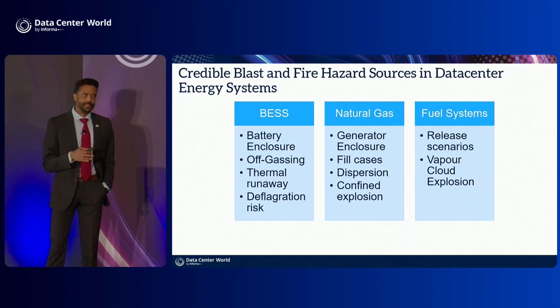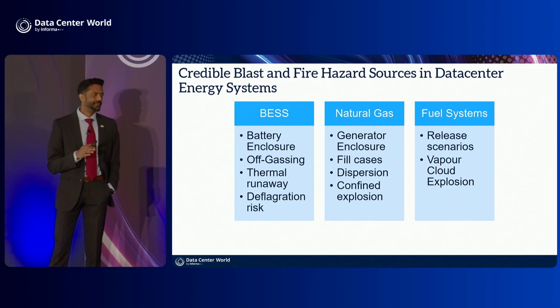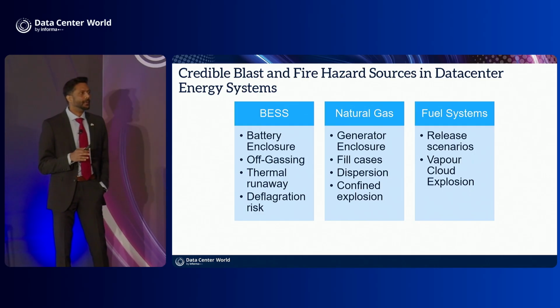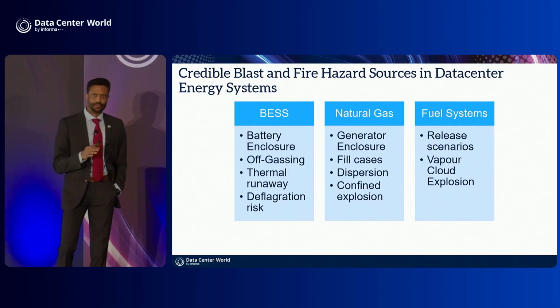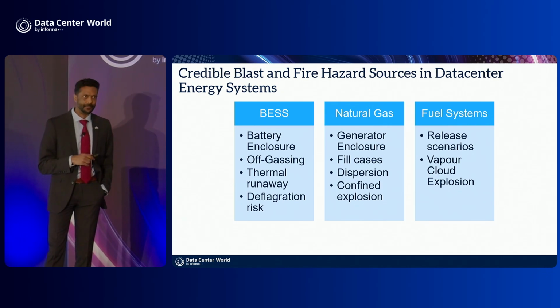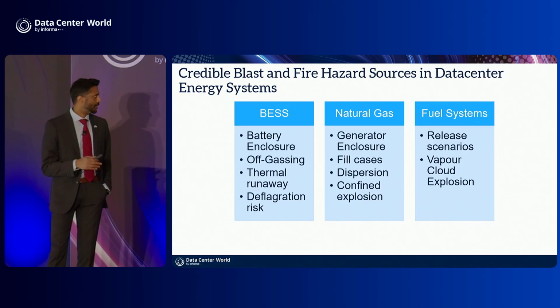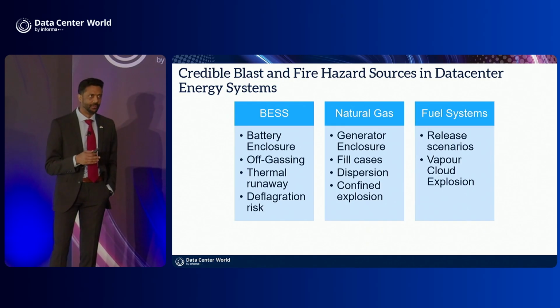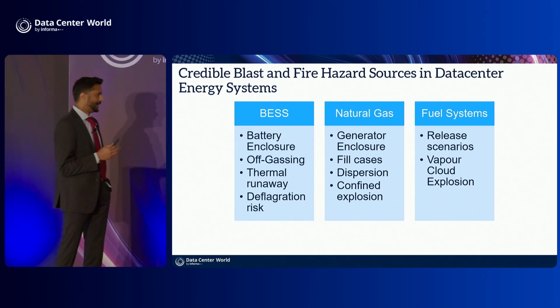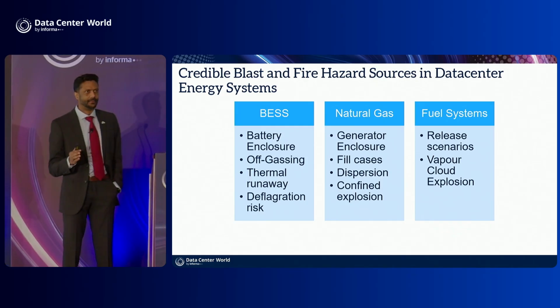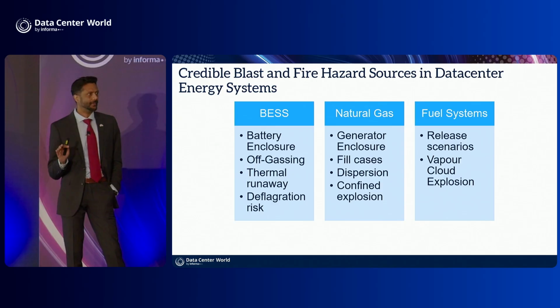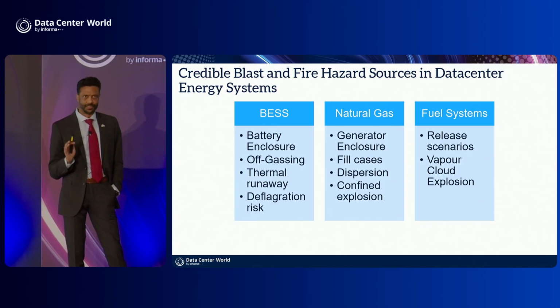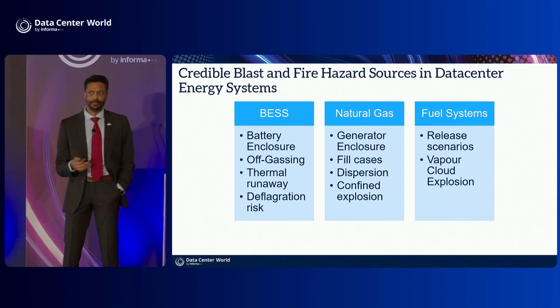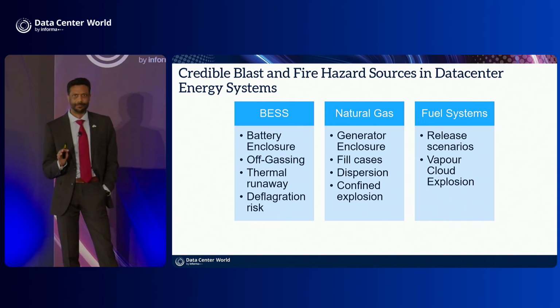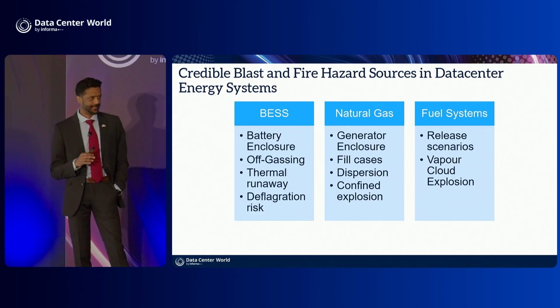The hazards associated with battery energy storage systems are well established, as anyone from the process safety industry can vouch for. These lithium-ion batteries used in BESS are often prone to off-gassing under heated temperatures. This off-gassing can cause thermal runaway and a cascading effect, causing a fire. Typically, once a battery energy storage system catches fire, you're told not to open it, let it burn. If you open it, it gets oxygen and can turn into an explosion. So you have to let it burn, which means the fire can last not just hours but days, which is a potential disruption for the data center.